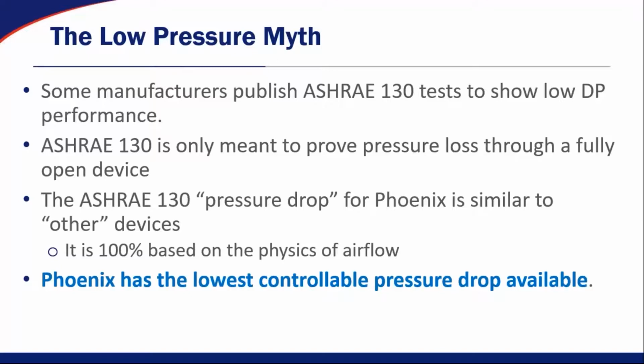controllability or the lowest flow that you can get at that pressure, but it doesn't really tell you that the device is in control. So the ASHRAE 130 pressure drop with a Phoenix valve versus other devices or third-party VAV boxes and things like that is similar because it's based on the physics of airflow. Basically, the only thing creating an obstruction or increasing the pressure per an ASHRAE 130 test is what's inside that valve. So Phoenix has a cone inside of the valve. Other devices like a bifurcated butterfly damper have a big section or a static regain compression section inside the valve. The only thing that changes pressure drop through a device that's fully open is what's inside the valve, the area that's being taken up in the dead air space of the valve.